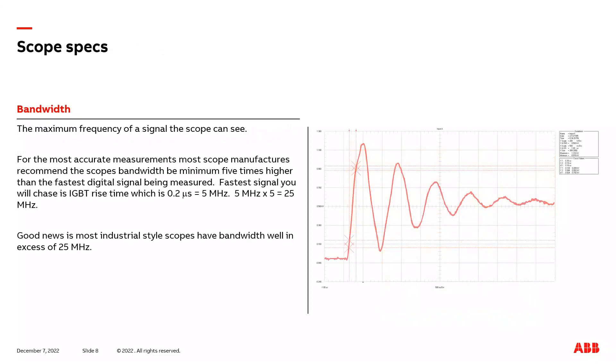I would now like to discuss two specification items that you want to make sure your scope has minimum ratings for so that you select the correct scope. The first spec item I'd like to discuss is bandwidth. Bandwidth is the maximum frequency that your scope can see. What does that mean? Well, for example, if the bandwidth of your scope had a max rating of 50 hertz and the signal frequency that you're trying to measure is 60 hertz, the scope would never see it. It would just be a flat line on the scope. So it's very important that your scope have a high enough bandwidth so that you can see fast signals that can occur on a VFD. Now, manufacturers recommend that scopes have a bandwidth rating five times higher than the maximum frequency of a signal you could be trying to measure.